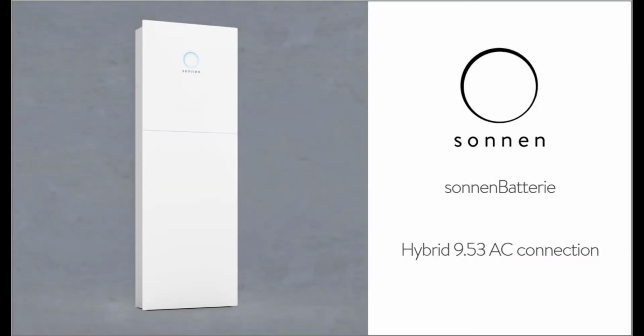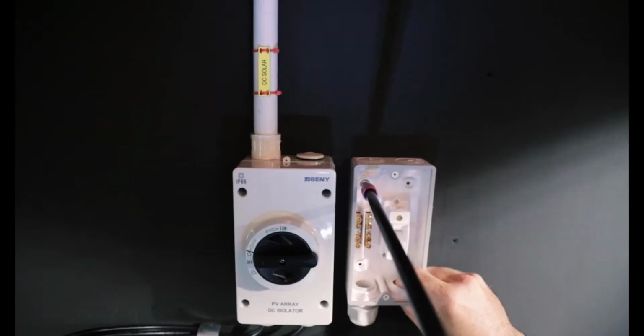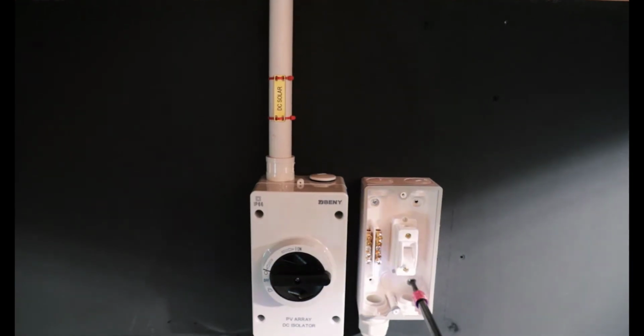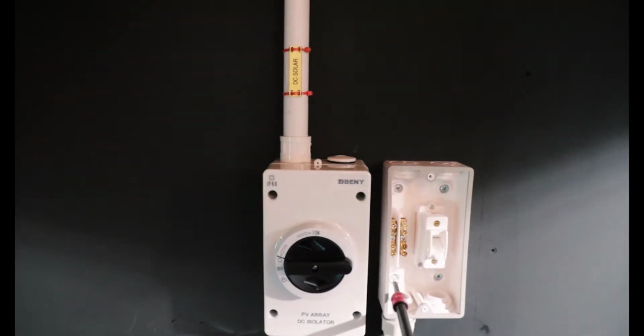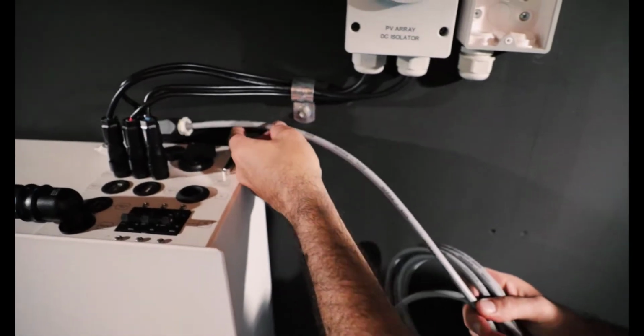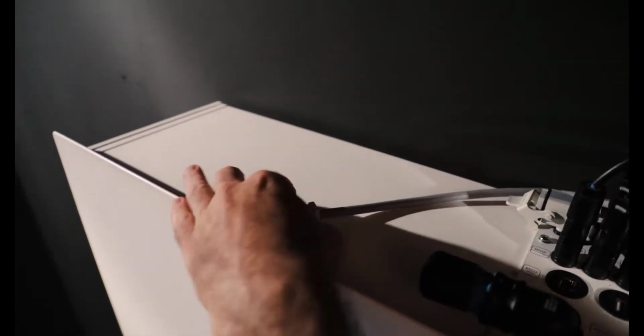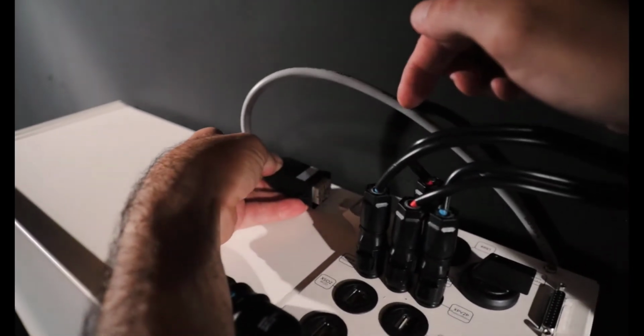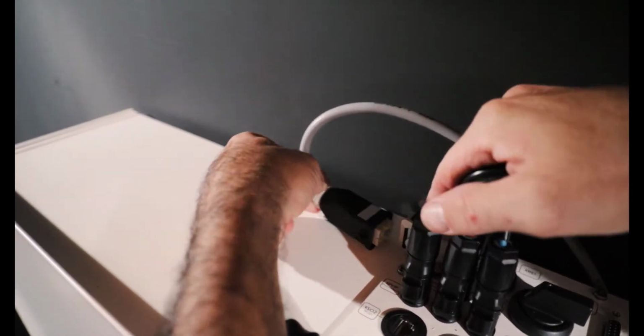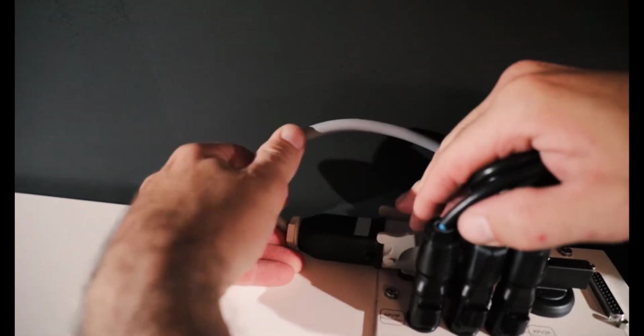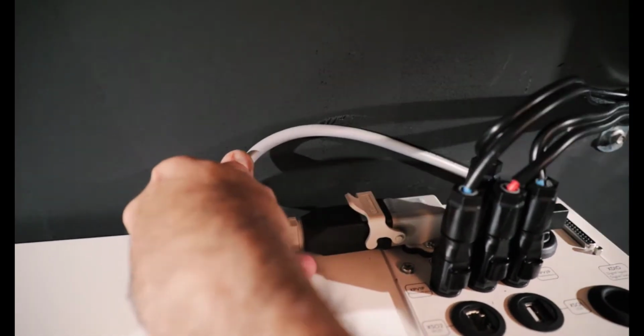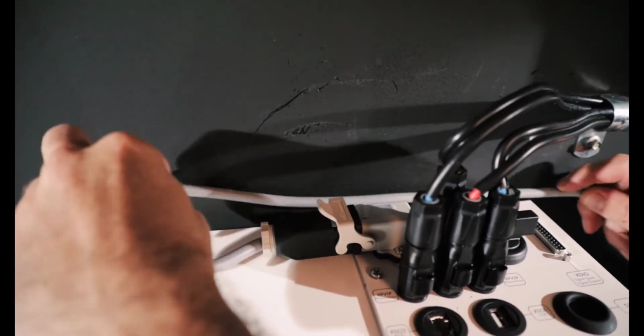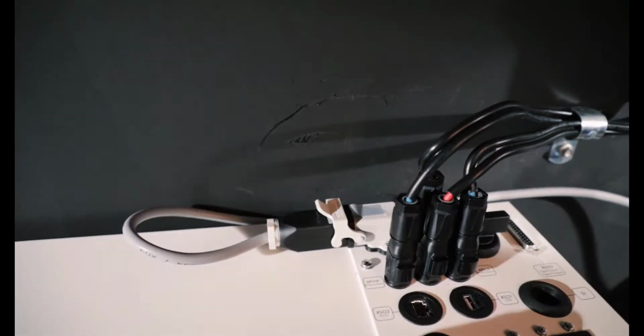The AC connections for the sonnenBatterie system: although the Sonnen system does have a plug, most inspectors nowadays do ask for an associated AC form of isolation. So this connector here is actually an applicable form of isolation under the eyes of AS3000. However, just to keep everything consistent with the rest of the industry, it is probably a good idea to put in an adjacent AC isolator. Obviously, if you're within 3 meters of the main switchboard, you don't need to worry about it.